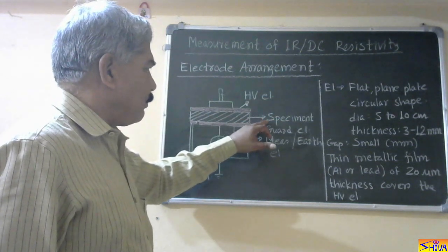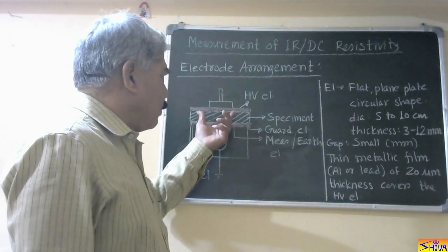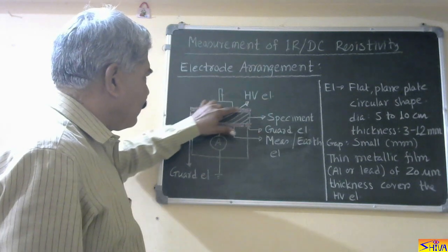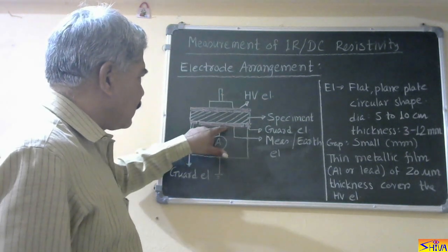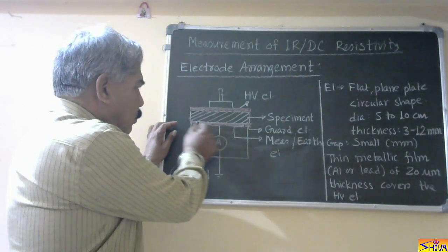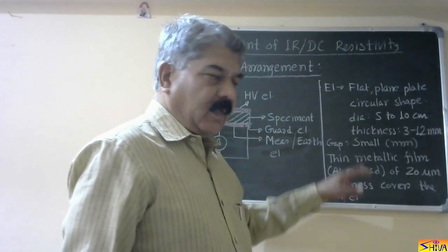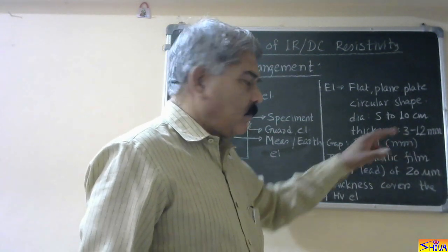The specimen is normally in a circular shape because the electrodes are also circular. There are three electrodes: the upper one is the high voltage electrode; the inside electrode is called the measuring electrode or earth electrode; and surrounding the measuring electrode is the guard electrode. The electrodes are circular plate shaped, with diameter 5 to 10 centimeters and thickness 3 to 12 mm.